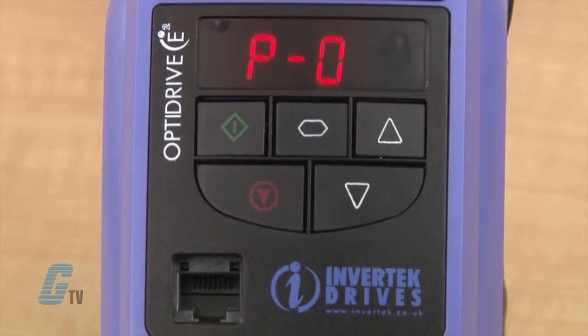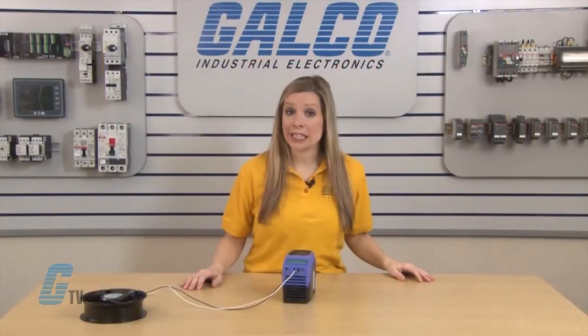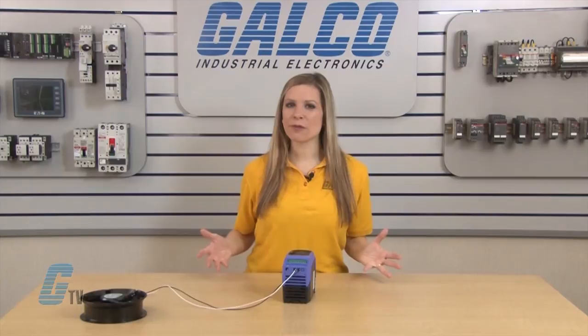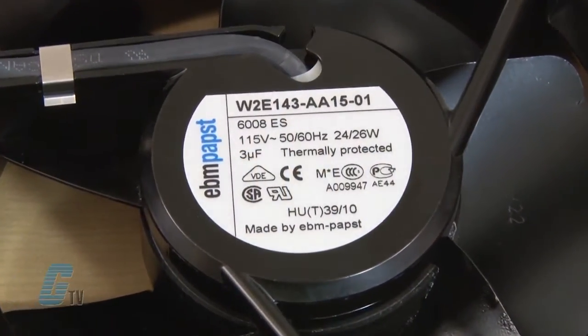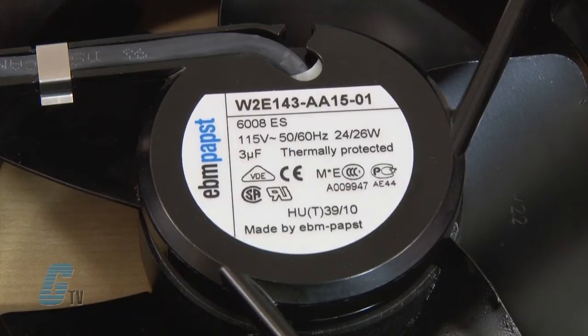I will go to P-7. From P-7 to P-10 is where I will plug in my motor data. This information is typically printed on the name plate of your motor and will differ from motor to motor. The motor I have is a fan from ebm-papst rated for 115 volts with 0.23 amps at 60 hertz.